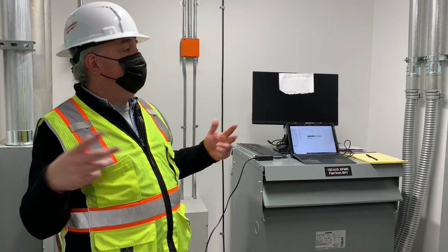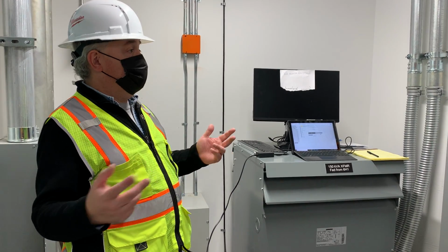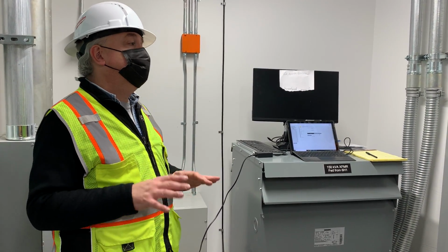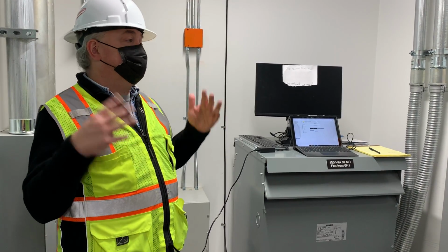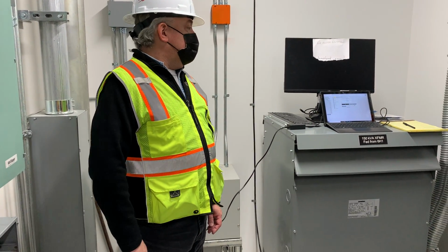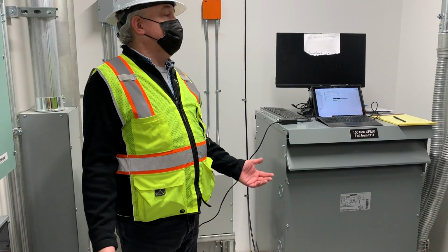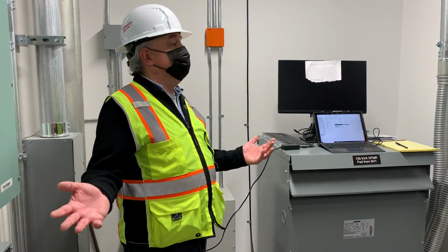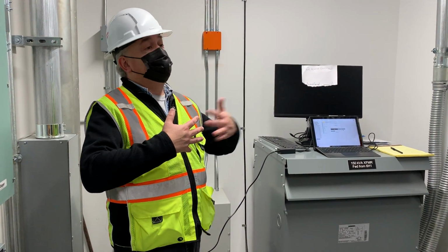There's a lot of air movement in there, and it's a very cold, very drafty environment, so I've reduced the ultrasonic settings in that space because it was false triggering a lot from air movement. So it just takes a little bit longer before they turn on. Generally, if you've got a door near a sensor, the ultrasonics will pick up the door opening because that's such a big change in the reflectivity of the space.